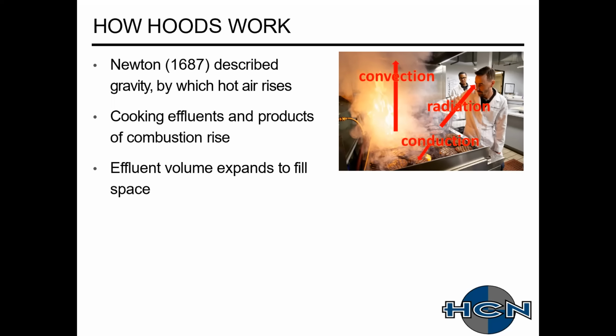There were a couple of ASHRAE standards in that previous slide that went over different heat gains to space. They did it, I think, in the 90s, and they did it again in the 2000s, because of changes in appliance technology, with appliances giving off a higher heat load. So it's a lot different than it was 10, 15 years ago. And then that effluent, when it heats, it rises and expands.